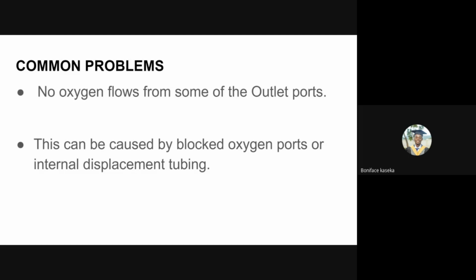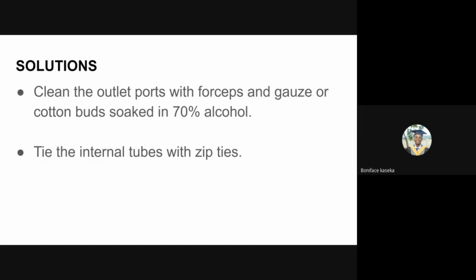So we're going to look at how you can solve such a problem. What you need to do is clean the outlet port with forceps and gauze. Sometimes we can also use cotton buds, they are good as well, but just make sure that you have soaked them in 70% alcohol. We normally use alcohol just to make sure that we do not infect the outlet port with germs. Because you are delivering oxygen to patients, and you don't want to infect them with other dangerous microbes. You can also check if there's an internal tubing problem.